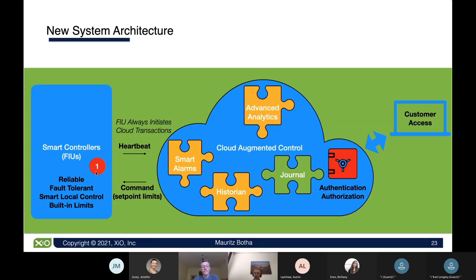Going back to the case of Oldsmar, they changed the sodium hydroxide level from 100 parts per million to 11,000. Smart controllers now can have limits saying you're not allowed to have a value outside a range of, say, 50 to 250. That way, even if somebody maliciously breaks into the cloud or accidentally changes a value beyond the limits, the controller would just ignore it.